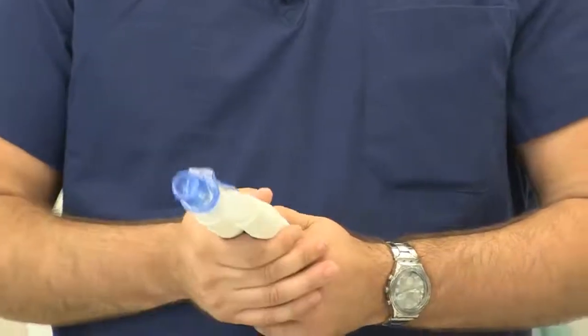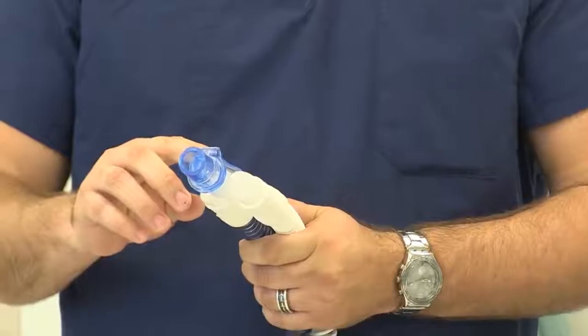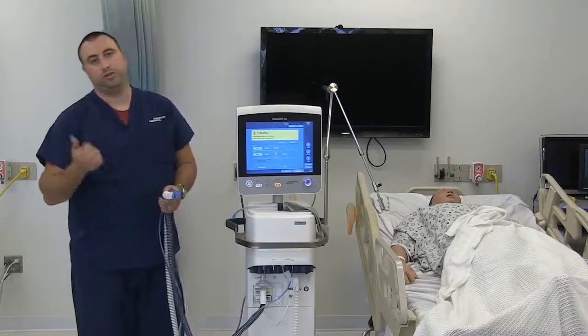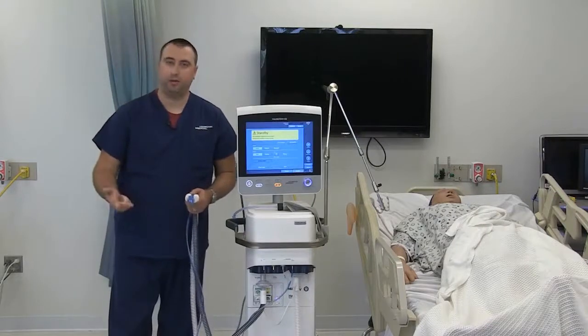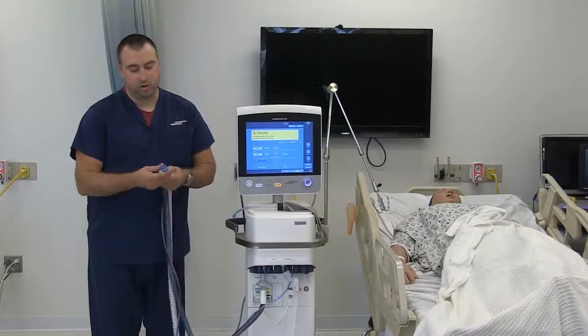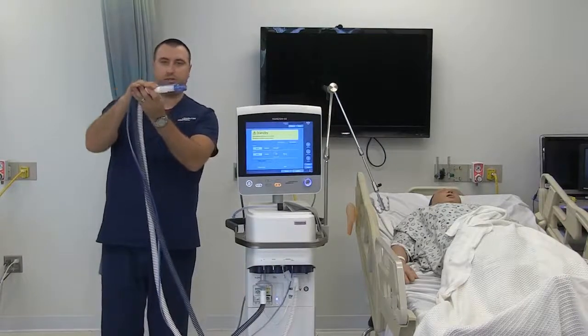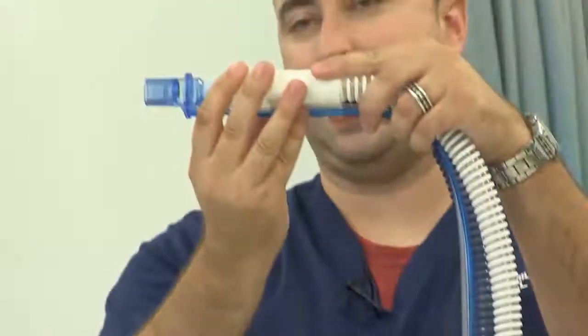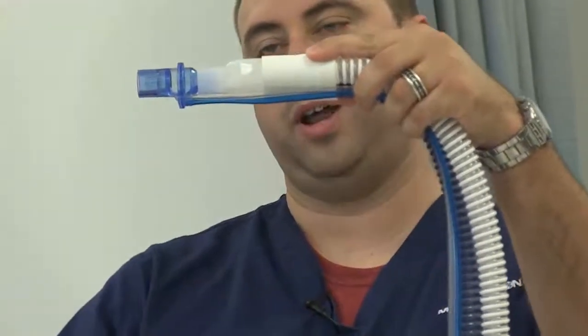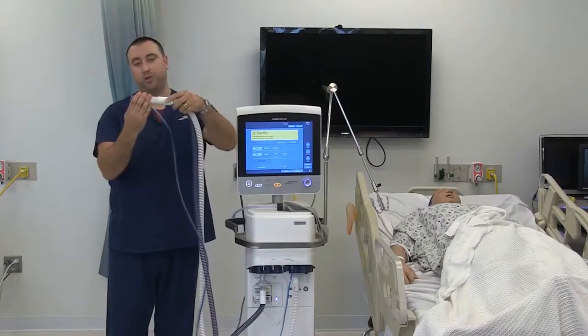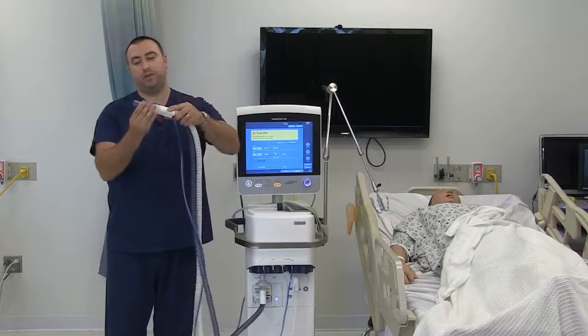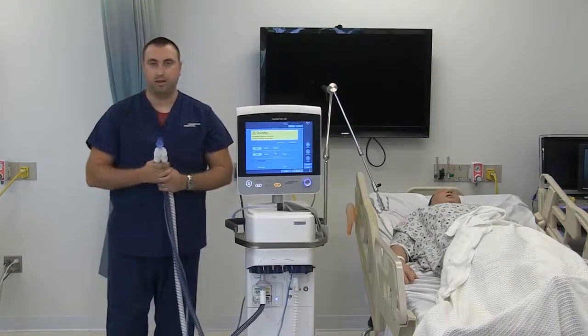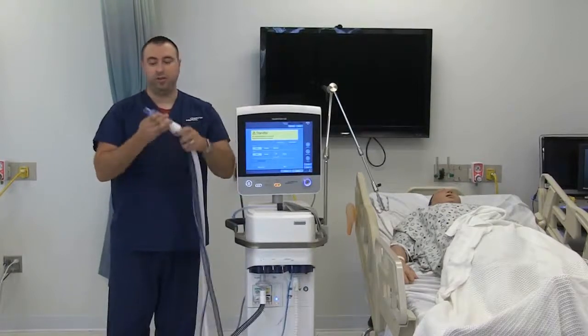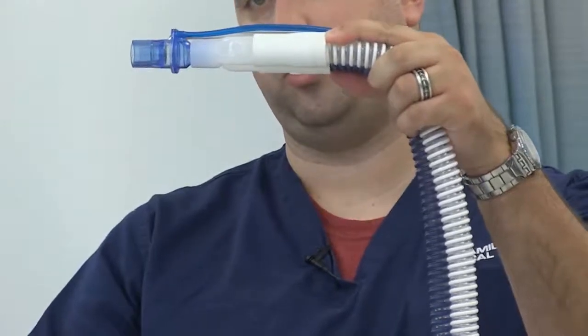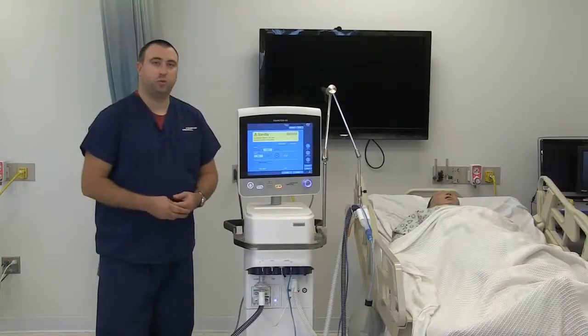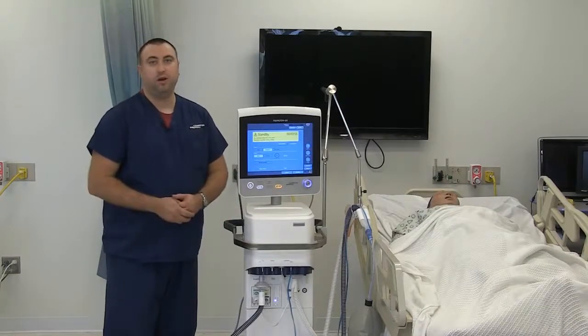There is a purge flow running through this flow sensor, and it will keep out your secretions, your nebulizer mist, and your rain out. But only if it is kept upright with the tubing pointed to the ceiling. If it is pointed down and there is a pool of secretions or rain out, creating a snorkel situation, this purge flow will not be effective and your flow sensor will not be able to get the appropriate data. So please reinforce to your staff and your nurses to be cognizant that your flow sensor tubing is pointed upright. Now I'm going to get into the actual application and usage of the Hamilton G5 on patients.